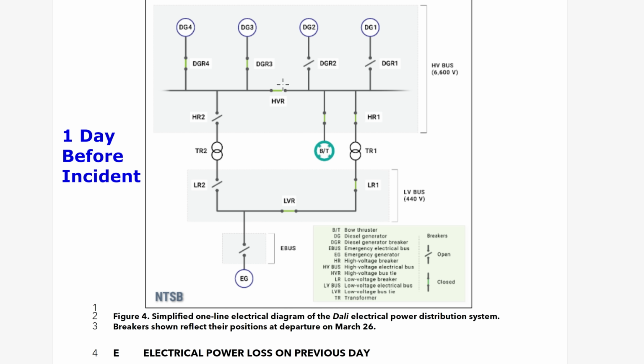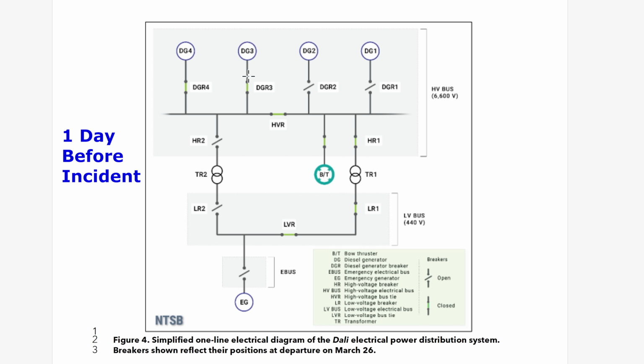So now you don't have any more 6600 volts, and then you don't have any more 440 volts. So they lost power to the entire ship. And so while this was spooling down, now you're looking here at diesel generator number 3 is up and running. But guess what? It's running low on pressure there. And so DG3 opened up, its fuse opened up. So now it's offline. So now we have another complete blackout on the ship again. And also during this time, they were now getting the power through this path here, through HR2 and LR2 instead of through HR1 and LR1. And then, of course, they finally reopened the damper here and got diesel generator number 2 running, and then everything was fine.